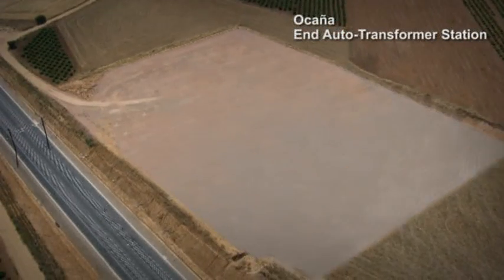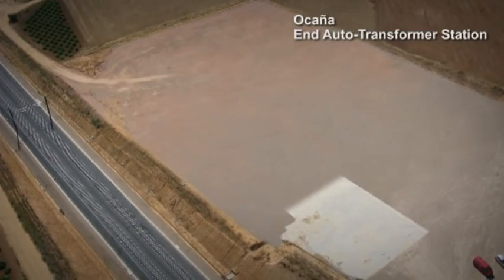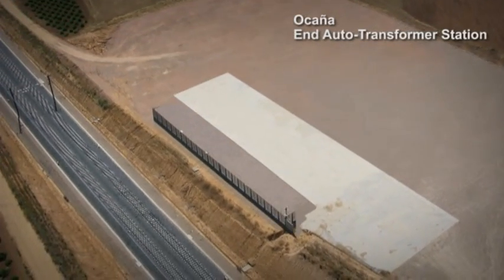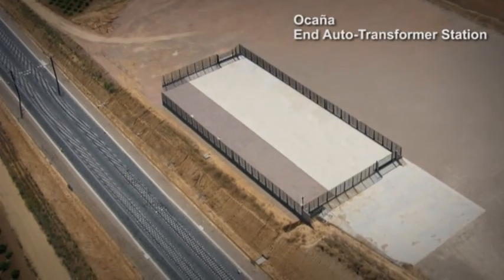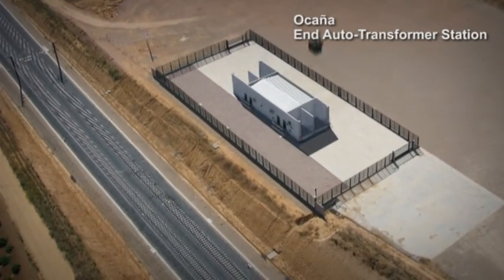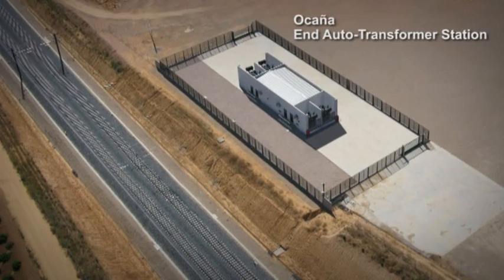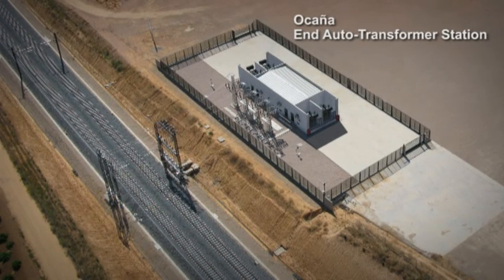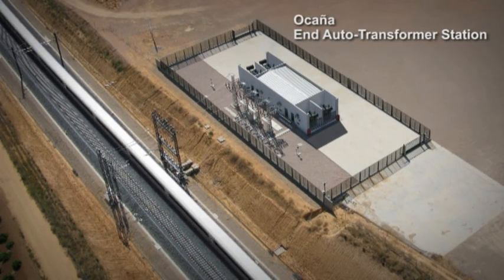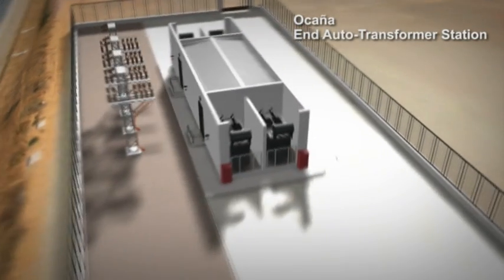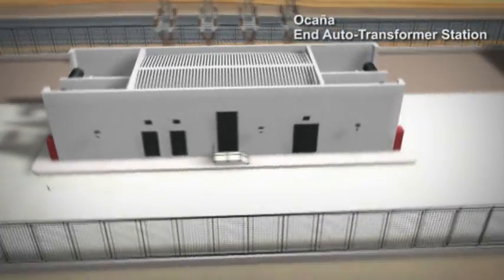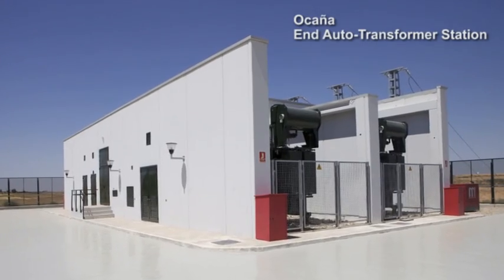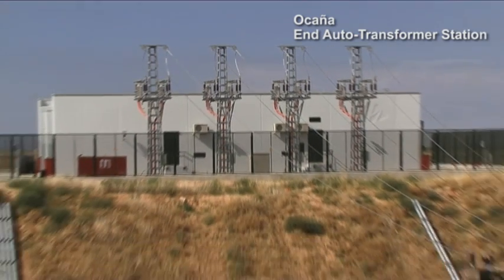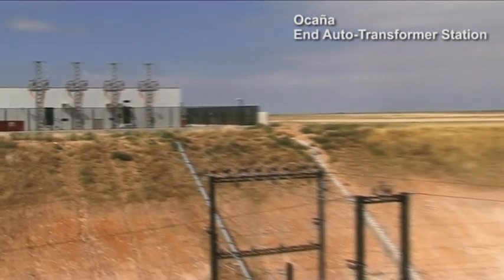Ocaña, end auto transformer station. A final auto transformation center is located between every 2 substations. This miniaturized substation is a fundamental element in the 2 by 25 system and has a dual purpose. On the one hand, it recovers the energy which comes from the substation via the negative feeder, which is fed into the overhead contact line and then to the train, hence reducing catenary voltage drop. On the other hand, if a substation fails, it can be used to power the collateral overhead contact line electrical section.